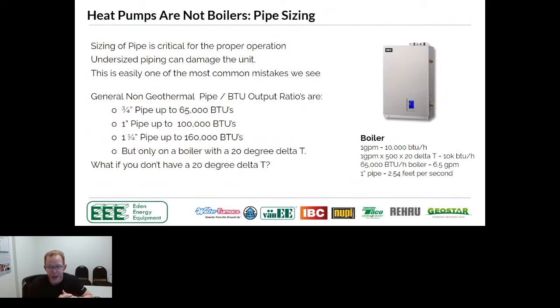We're trying to do it in an hour, so I'm moving quickly. As we look at some of the earlier points, we talked about pipe sizing and knowing the difference between a hydronic heat pump and what is required for a boiler. And I've given some examples here. If we look at the 2 to 4 feet per second rule on copper piping, with 3/4 inch pipe, 65,000 BTUs, give or take, and 1.25 inch pipe up to around 160,000 BTUs.